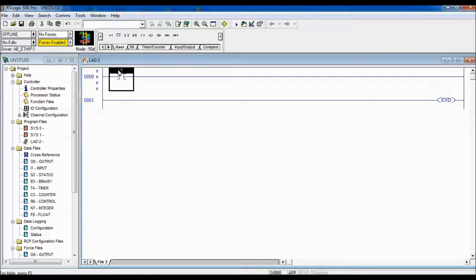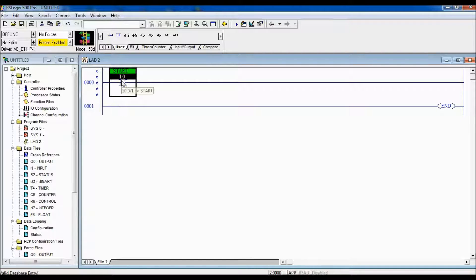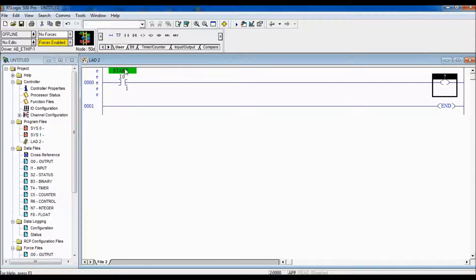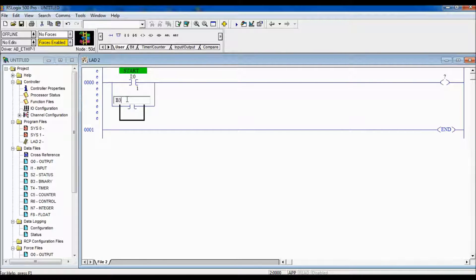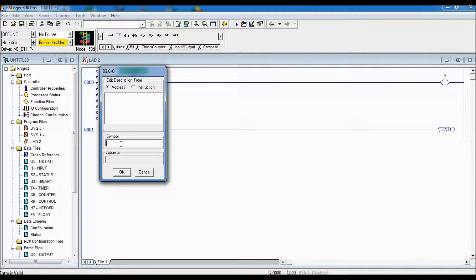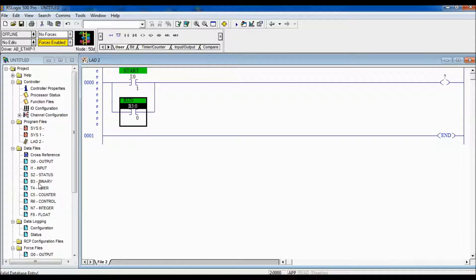I will insert a rung and we'll enter the start push button. The start push button is located on input I colon zero slash one. When the start push button is pressed, our run bit will go true and it will stay true until the stop push button is pressed. I create a memory bit location for our run bit, which is going to be B3 colon zero slash zero, and I call that 'run'. Remember, our binary bit location is just a storage location in memory that we can use to store logic such as the run bit.